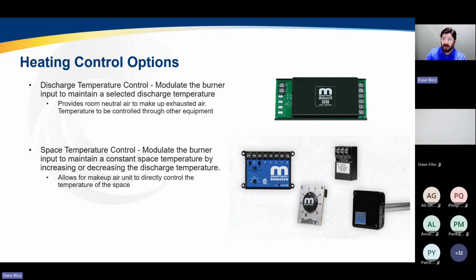Secondly, depending on your application, maybe this makeup air system is going to provide my ventilation and my space heating requirements. So now I actually want to modulate my discharge temperature maybe above neutral air. So I want to go above, say, my 65-degree indoor set point. But as the ambient conditions change, temperatures, infiltration, other things might change throughout the season. Now I actually want to be able to modulate my discharge temperature up and down to maintain a space temperature. Those are two different options, but ultimately it's all about what does the customer want? What's the indoor environment and problem I'm trying to solve? How do I want to vary my airflow and my temperature and my heating source to make sure we're providing that, again, seamless indoor air quality consistently across a highly variable operating environment.